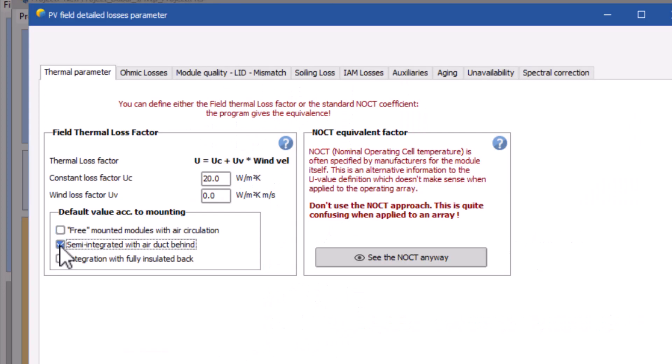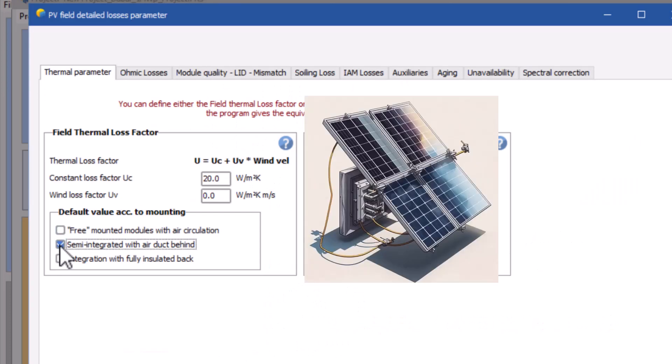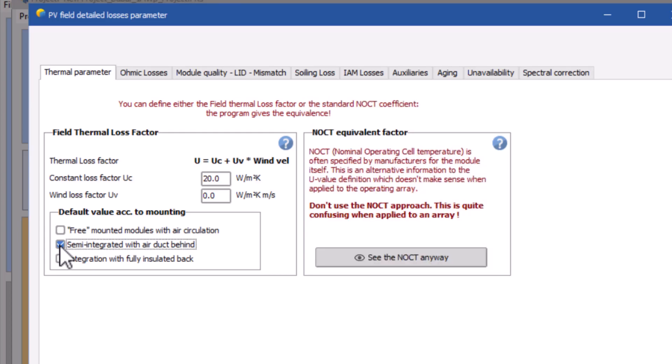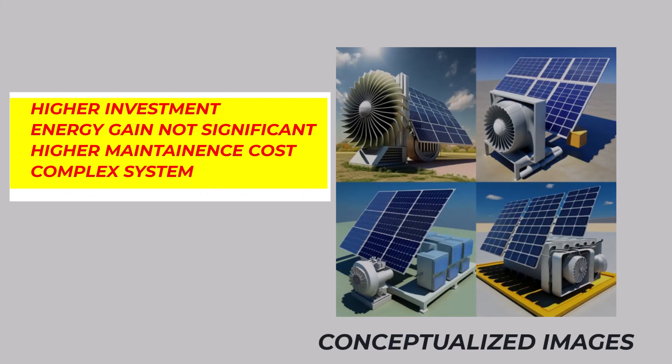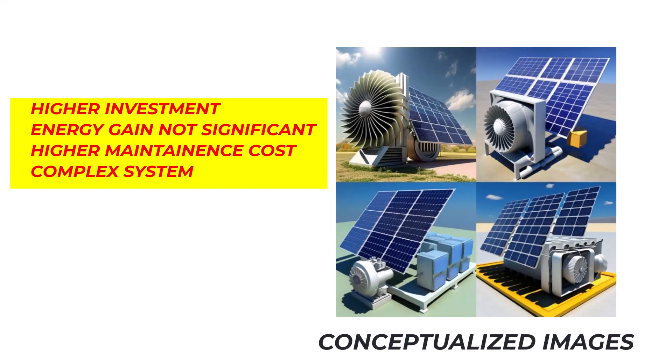The second option is semi-integrated with air duct behind. This means an external arrangement to naturally or forcefully blow air at the back side of the PV module, so that it loses temperature by convection and the temperature will be lower. This type is very rare nowadays as it adds capital investment and the energy gain from such an arrangement is not attractive compared to the complexity and cost.